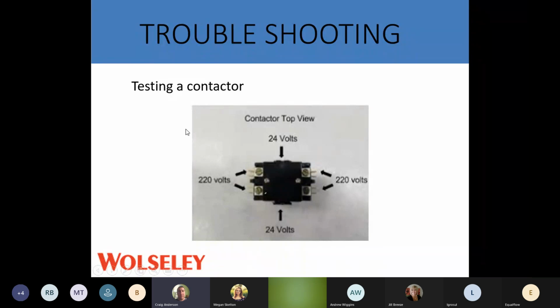So when we're checking 220 volts, we're going from L1 to L2. We're not going from L1 to ground or L2 to ground. There are panels out there that allow you to put a breaker in that only allows you to take it from one leg of the panel. So when you go outside and you're going from ground to L1, it's going to tell you that you've got 110. L2 to ground is going to tell you that you have 110. But when you go across L1 to L2, it's going to read 0. That means you don't have 220 volts out there. You have 110 on each side.